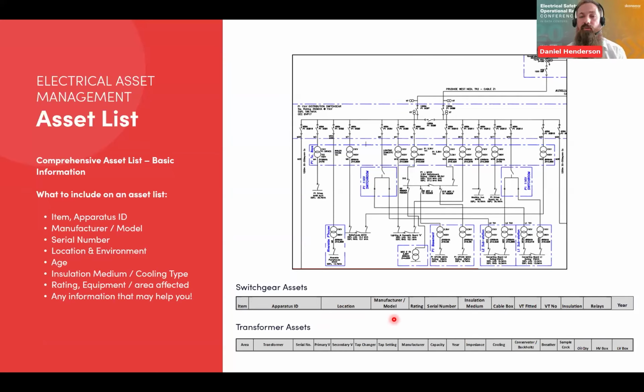The manufacturer and model, so who made the asset and the model of the asset, and the rating of the asset. If it's switchgear, it'll be in amps. If it's a transformer, it'll be in kVA or MVA. The serial number: typically every panel or every key component will have a unique serial number. Again, from a traceability perspective, which we'll come to later on, it's important. For switchgear, what's the insulation medium? Is it gas insulated switchgear? Is it oil? Is it vacuum? Is it air? That's good to know, and it can be important from a risk perspective. In some geographical locations, if it's gas insulated switchgear, it might be a greenhouse gas, and over a certain quantity by weight, you might need to record that from a legislation perspective.